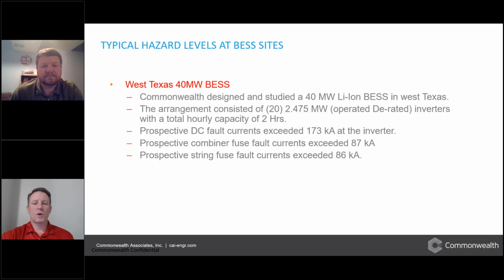So I wanted to go over some of the typical hazard levels at some of our sites we looked at. We put in a very large battery system in West Texas. This was not a central inverter. This had about twenty 2.475 megawatt inverters. And sometimes the arc flash is worse if you raise the hourly capacity to like an 8-hour battery, but this one was 2 hours. And even with that, it was still incredibly high fault currents on the DC side just because of the size of it.